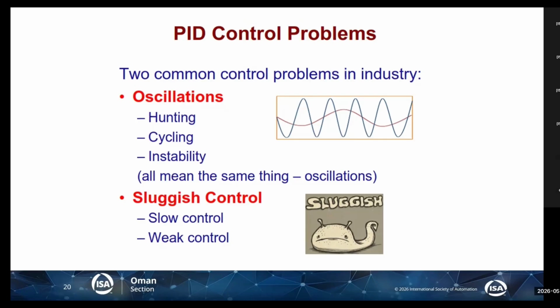Okay, what we have to do is investigate and diagnose to check whether it is a controller issue or another issue, because in a lot of cases it is not a controller issue. It can be a valve having a problem, an old or sticky valve, or whatever. It can be an instrumentation issue, whether it is physically damaged or has the wrong range. It can even be some logic issue, and we have seen this in the industries.